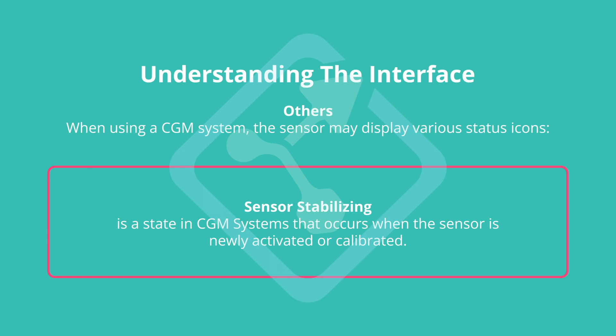Sensor stabilizing is a state in CGM systems that occurs when the sensor is newly activated or calibrated, where it is adapting to the internal body environment and adjusting its parameters for accurate blood glucose readings. This requires some time, possibly lasting several hours. Change a new sensor is a warning in CGM systems to replace the sensor. This status appears when the current sensor reaches the end of its designed lifespan or if the sensor is malfunctioning.